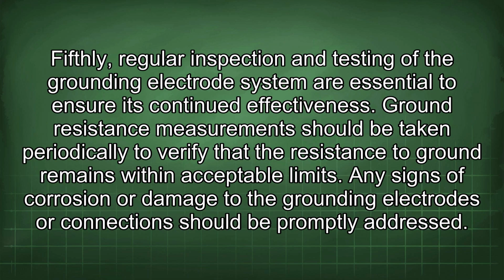Fifthly, regular inspection and testing of the grounding electrode system are essential to ensure its continued effectiveness. Ground resistance measurements should be taken periodically to verify that the resistance to ground remains within acceptable limits. Any signs of corrosion or damage to the grounding electrodes or connections should be promptly addressed.